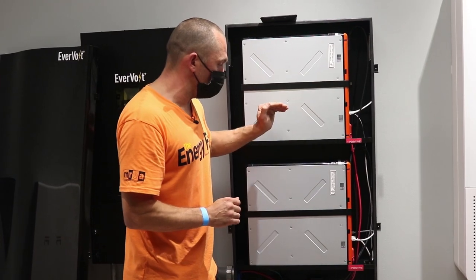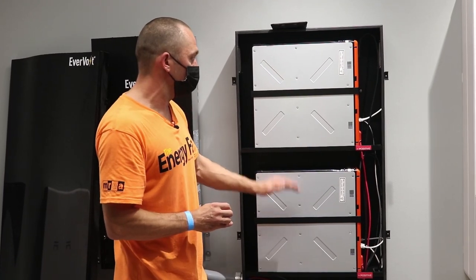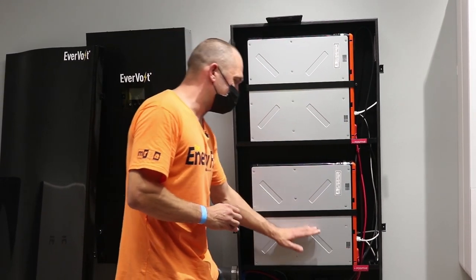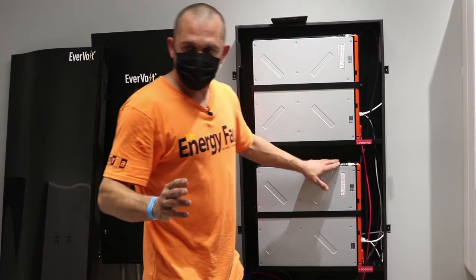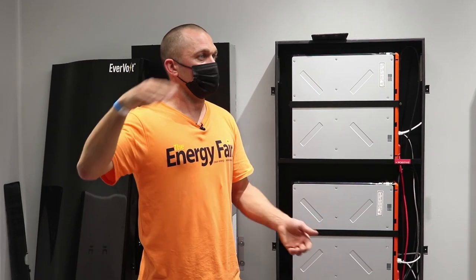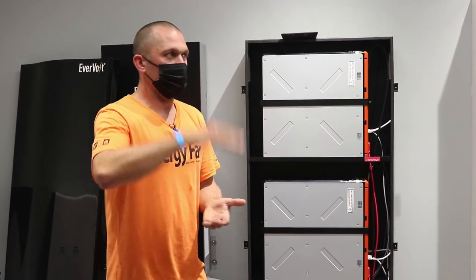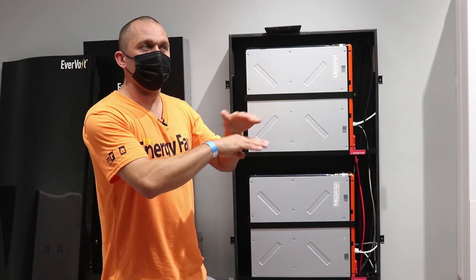That allows varied charge and discharge patterns. With lithium-ion batteries, a big difference from lead acid is they can discharge very low. With nickel manganese cobalt and lithium iron phosphate chemistries, you can discharge 100% — take the battery all the way down to 100% depth of discharge — and it's perfectly happy. You can bring it all the way down and bring it back up; that's part of the cycle.